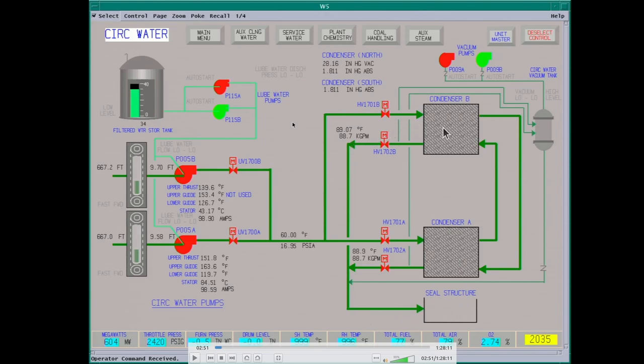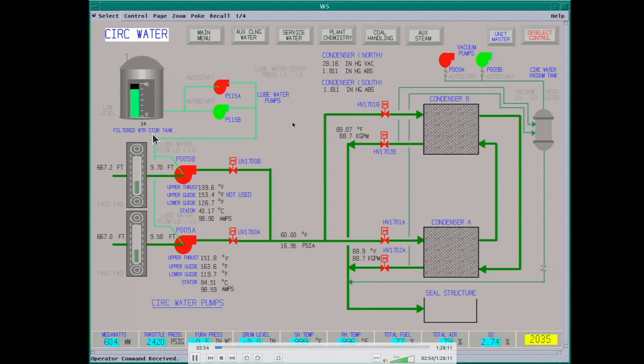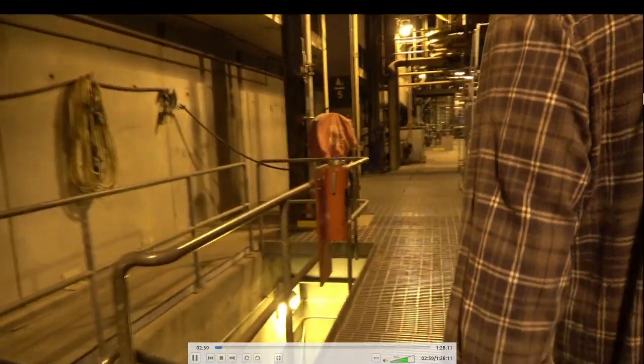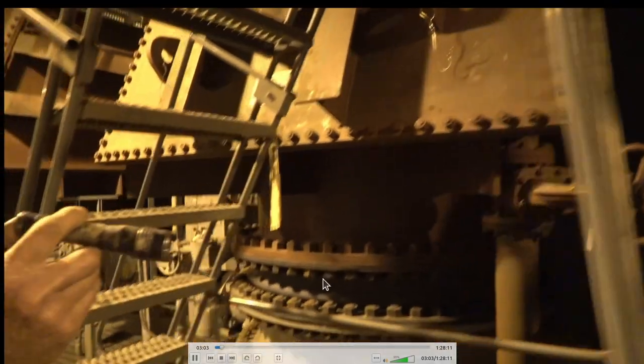There's a vacuum tank and vacuum pumps — these pull vacuum on the upper tubes to keep any air out so the surface condenser doesn't airlock. The seal structure helps minimize pump power usage by creating a siphon effect. These are the water boxes of the surface condensers, with drain valves on the side and your main butterfly valves.